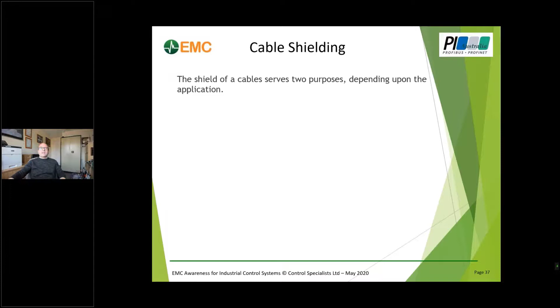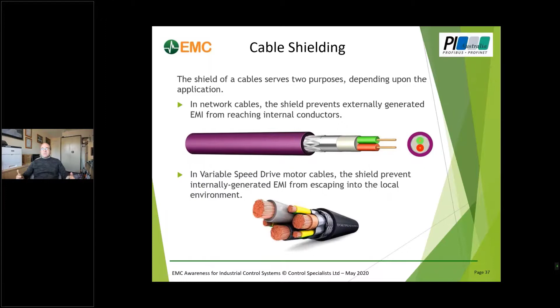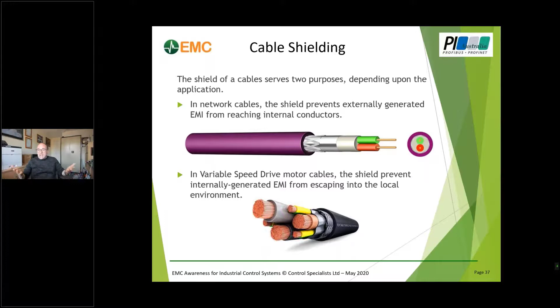Okay, what about shielding then? I'm now talking about the shielding on cables, assuming the cable has a shield. The shield has two purposes. First, in network cables, it's to prevent externally generated EMI from getting into those conductors and corrupting the ones and zeros on our data stream. In a variable speed drive, it's the opposite - we want to keep the emissions from the pulse width modulation inside from getting outside. The bottom line is the importance is the same in both cases.